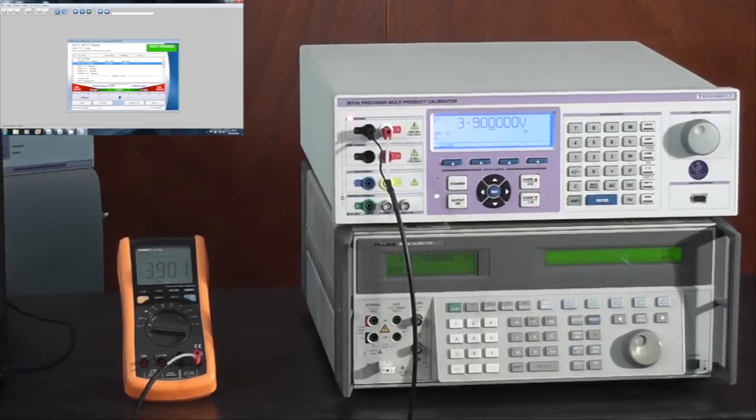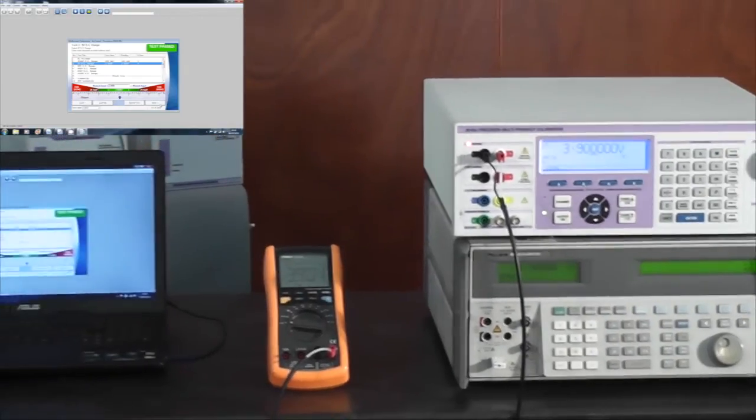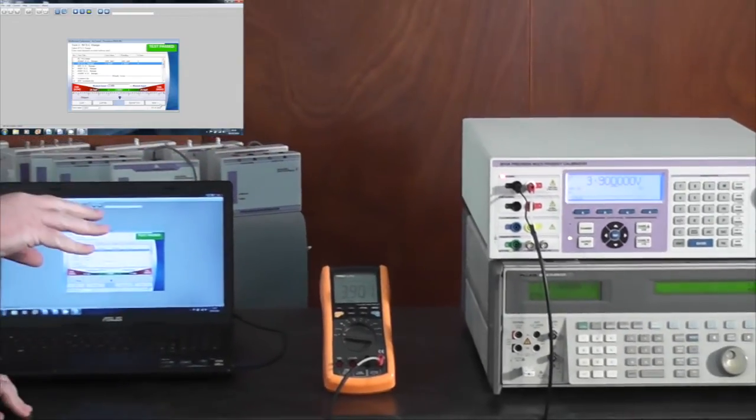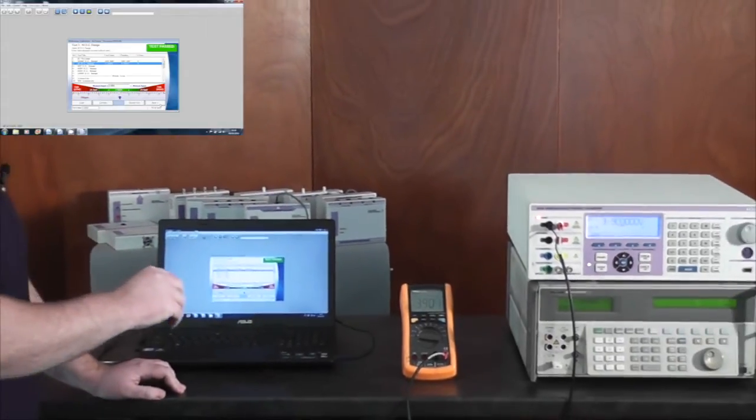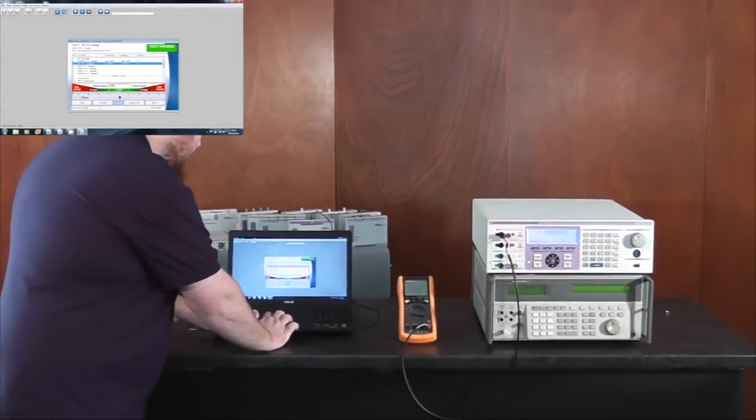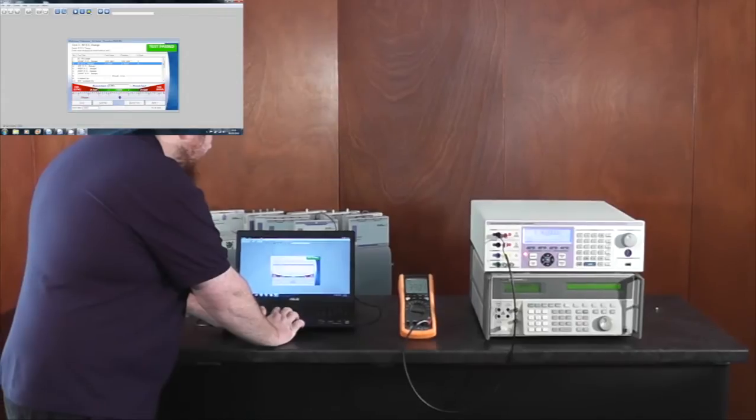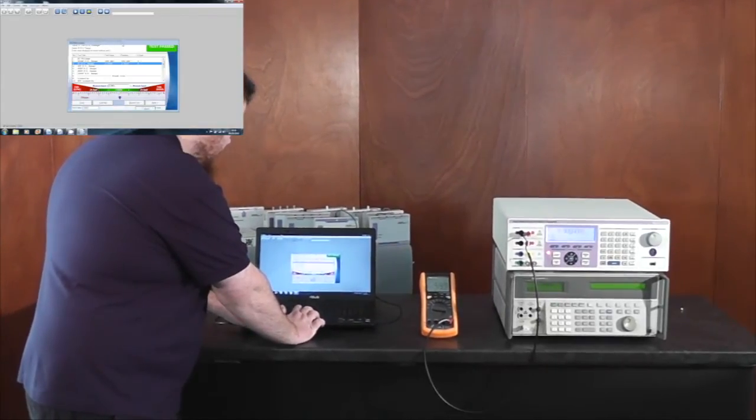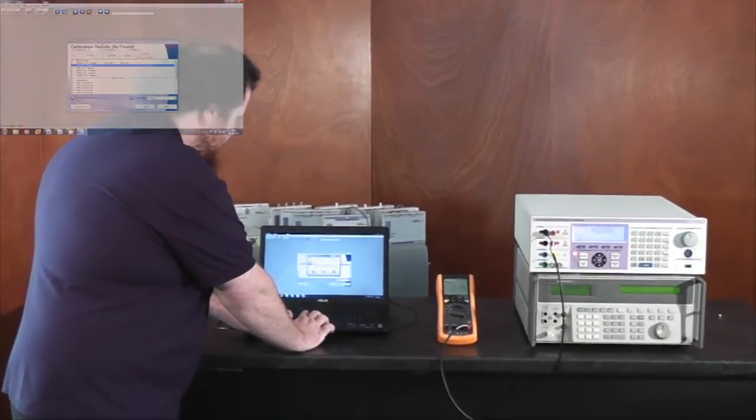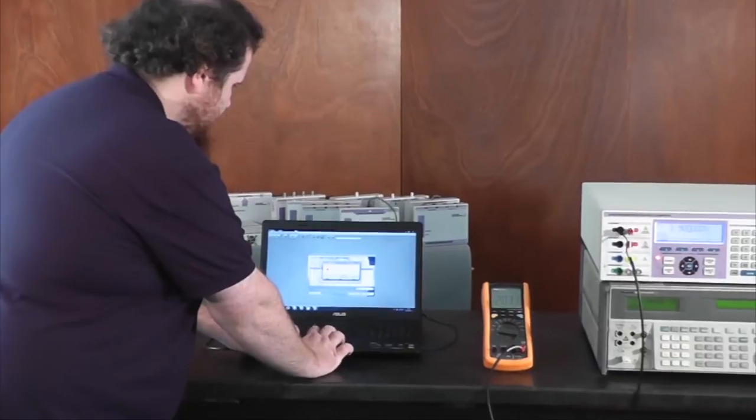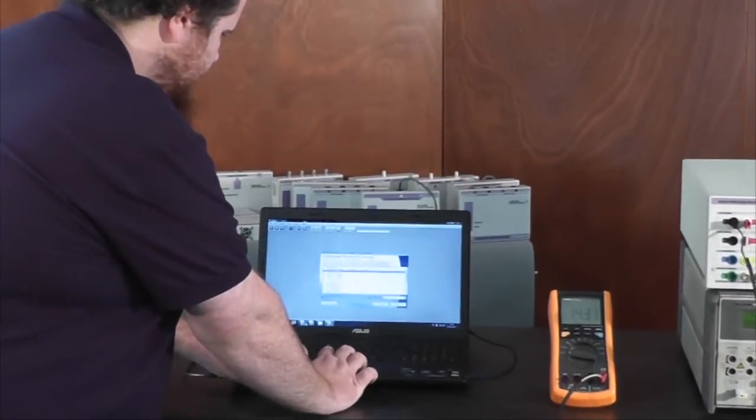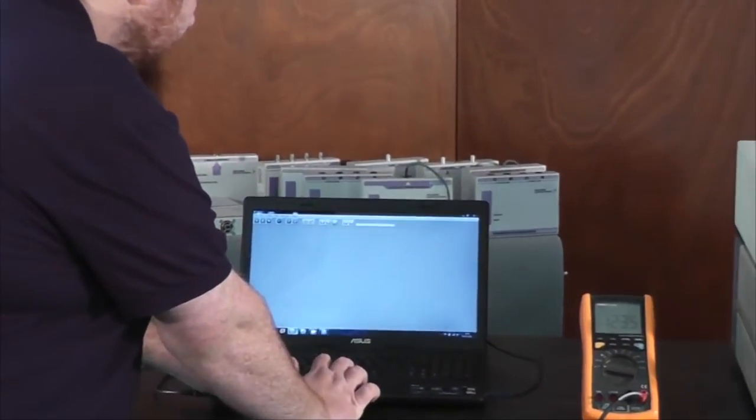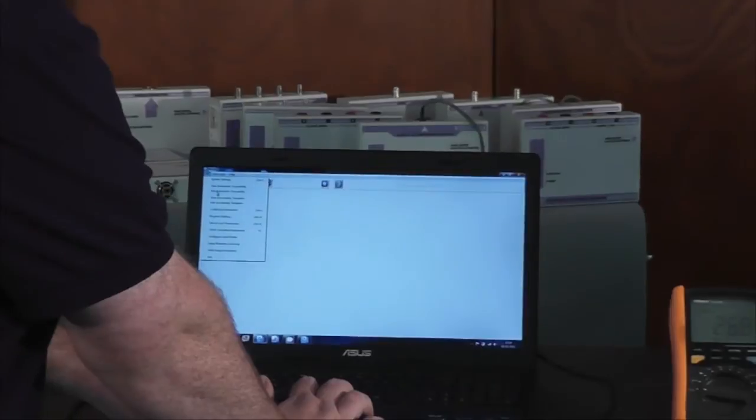Now I'm going to quickly switch over to using the Fluke calibrator in place of the Transmille units. This is as simple as aborting the existing calibration and opening process.